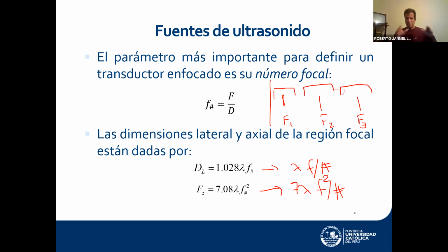And you can stitch the images that these 3 transducers would produce, so you have one portion of the image, then another portion, then another portion, and somehow most of the image is in focus. So you can create those composites of images, which is actually the way every echographic image is composed in practice nowadays.